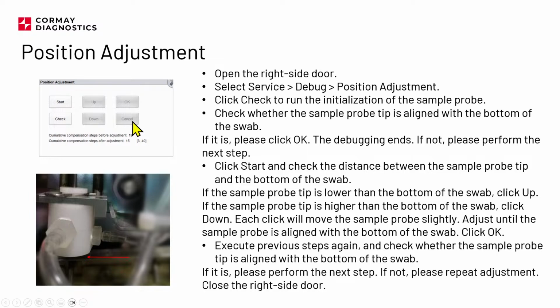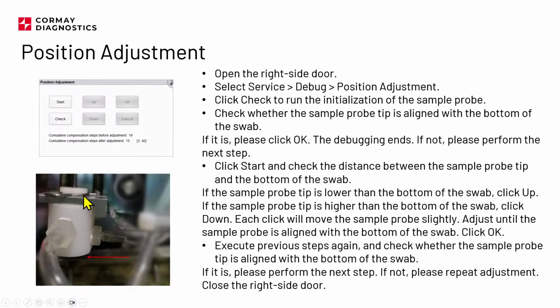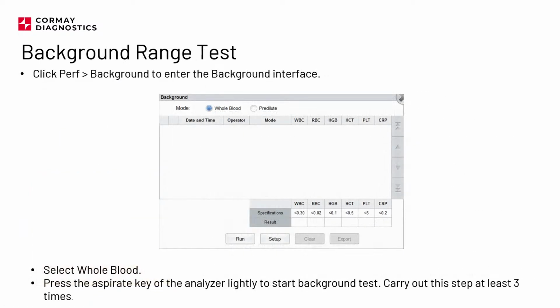That is also okay, and cancel this process, right? Okay, saving. Cancel is canceling this whole process, and check is just for checking. So the analyzer is just adjusting the position, and this allows you to check this thing. By the way, this procedure will be needed when you replace the sampling needle, but during the installation, it's just a recommendation to see if this is correct, and just set it if needed.